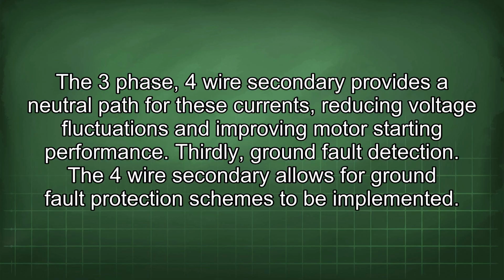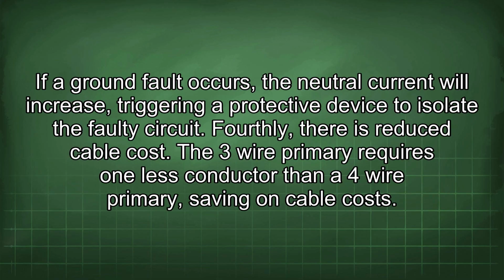Thirdly, ground fault detection. The 4-wire secondary allows for ground fault protection schemes to be implemented. If a ground fault occurs, the neutral current will increase, triggering a protective device to isolate the faulty circuit.